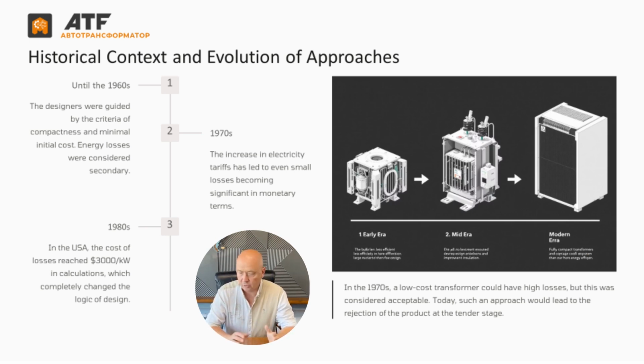Until the 1960s, transformer design was based on two priorities: compact size and low upfront cost. Energy losses were considered secondary. But in the 1970s, things changed dramatically. Electricity prices rose, and even small losses started to carry significant financial impact over time. This gave rise to a new economic concept: loss capitalization, meaning the monetary value of energy losses over the entire lifetime of the transformer. For example, by the early 1980s in the U.S., engineers began factoring in the cost of losses at a rate of up to $3,000 per kilowatt of lost energy. This changed the logic of design itself.